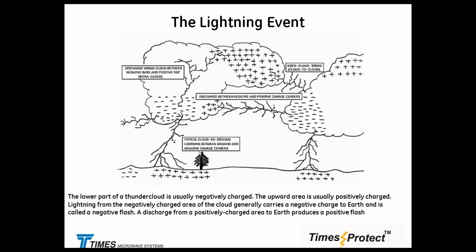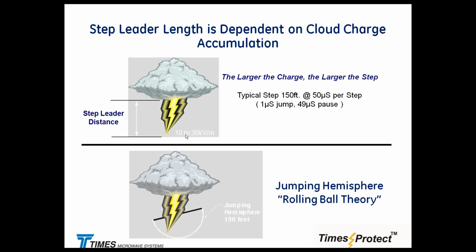And at a given point in time, when the step leader coming down and the opposing streamer connect, you are going to have basically a free current flow. And typically the impedance of the plasma channel or the conductive channel for the event will be in the range anywhere from 10 to 20 ohms. I don't want to spend too much time on the theory of it. So if you take a look at the typical step leader right here, the potential will be somewhere in the 10 to 30 kilovolts per meter.